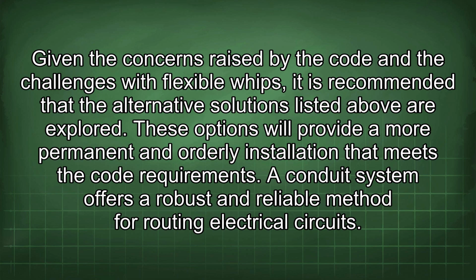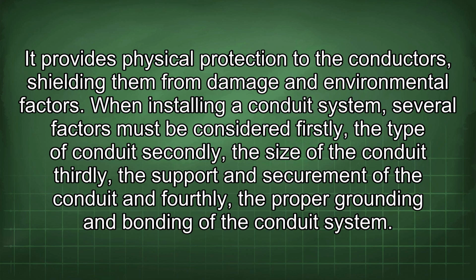A conduit system offers a robust and reliable method for routing electrical circuits. It provides physical protection to the conductors, shielding them from damage and environmental factors. When installing a conduit system, several factors must be considered. Firstly, the type of conduit. Secondly, the size of the conduit. Thirdly, the support and securement of the conduit. And fourthly, the proper grounding and bonding of the conduit system.